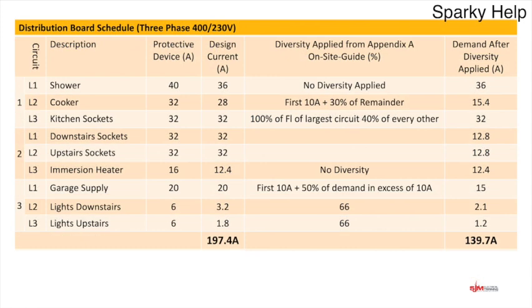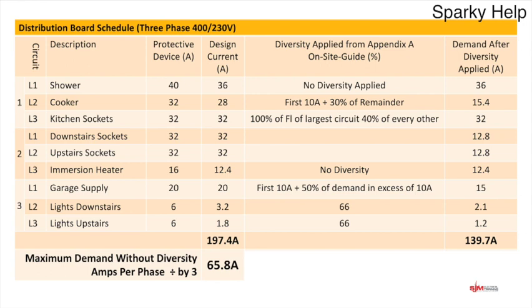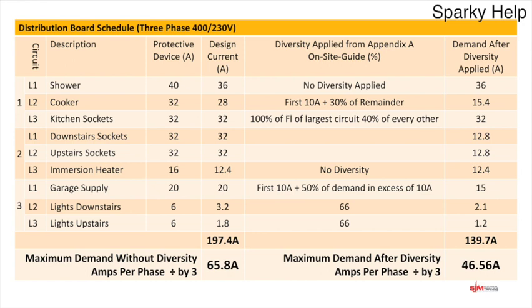Now let's look at a three-phase example with the same circuits spread over three phases. The maximum demand without diversity is still 197.4, and with diversity 139.7 — but this is over three phases, so we divide by three to get amps per phase. Without diversity: 197.4 ÷ 3 = 65.8 amps per phase. With diversity: 139.7 ÷ 3 = 46.56 amps per phase. Adding individual phases up is difficult and won't be accurate due to the way the calculation works, so dividing by three gives the best approximation.